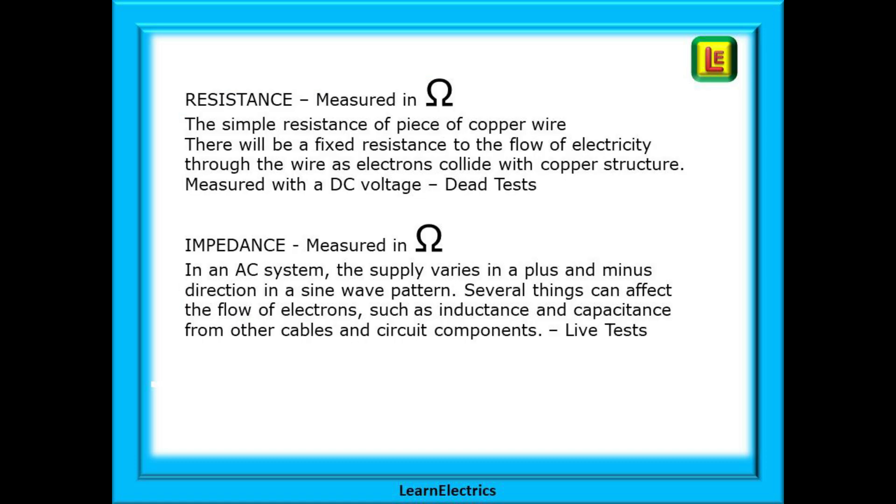Before we begin we must understand these two words. The first is resistance and this is measured in ohms. Here we are interested in the simple resistance of a piece of copper wire. The copper will show a fixed resistance to the flow of electricity through the wire as electrons collide with the copper structure. It is measured with a DC voltage around four volts and just fractions of an amp and it is a dead test.